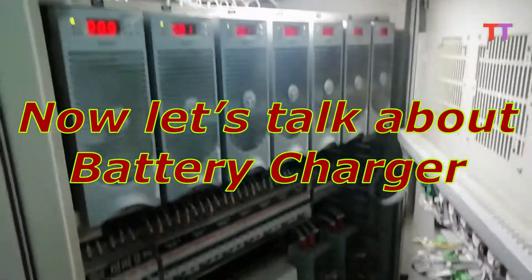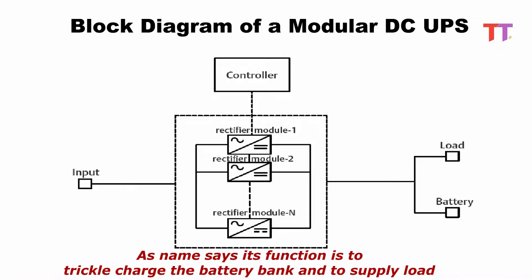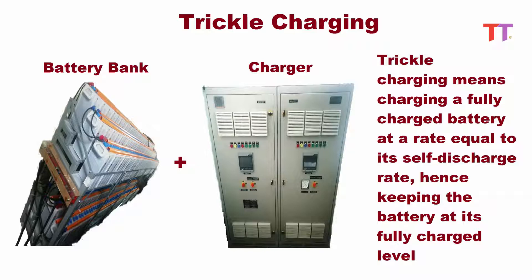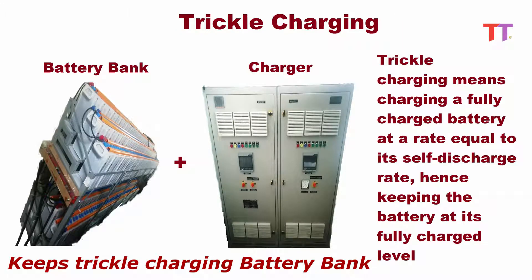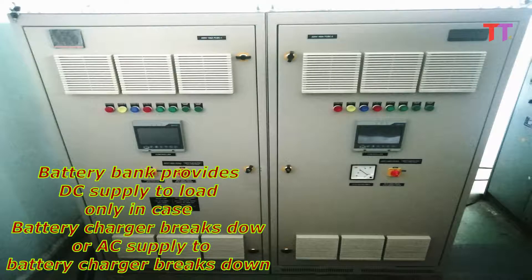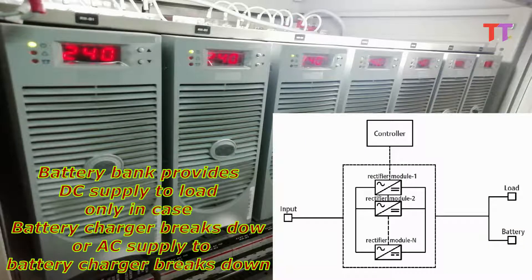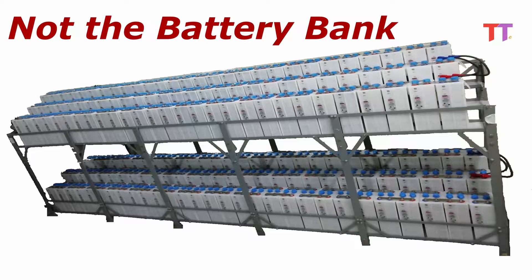Now let's talk about battery charger. Battery charger is nothing but an AC to DC converter, and as the name says, its function is to trickle charge the battery bank and to supply DC power to the load. Trickle charging means charging a fully charged battery at a rate equal to its self-discharge rate, hence keeping the battery at its fully charged level. In normal condition, the charger provides DC supply to the load and keeps trickle charging the battery bank. Battery bank provides DC supply to the load only in case the battery charger breaks down or AC supply to the battery charger fails. So in normal condition, it is the charger which supplies DC power to protection, communication, control, and measurement devices in the electrical substation — not the battery bank.